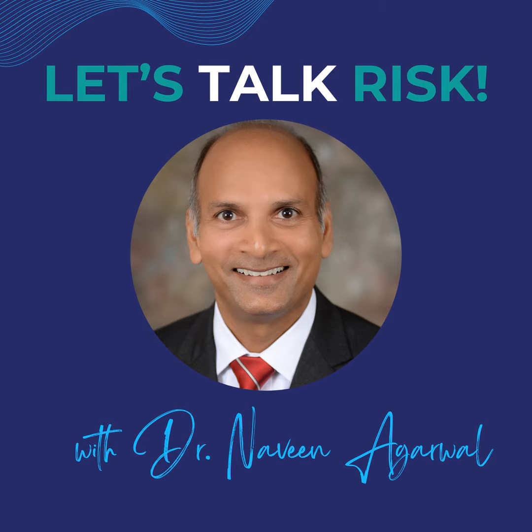So, Alex, while we wait for people to join, I want to touch upon another topic that is very close to my heart, and that is system safety. You're the best person to help us understand, at a higher level, that a medical device is a system. It operates in a complex environment. Help us understand why following some principles of system safety is beneficial for risk management. So I think the real critical element that I've observed is the functional analysis, so knowing and having clarity on what part does what, or is expected to do what.